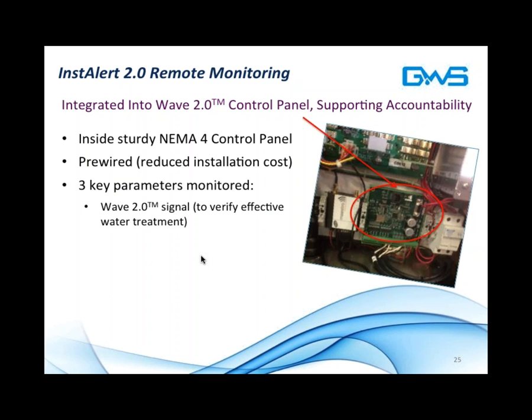The first is that the Wave is doing its job, which is to say that effective water treatment is taking place, another way of ensuring that scale is under control, corrosion is in check, and biological growth is effectively being treated. The second parameter is conductivity of the recirculating condenser water. This allows us to infer if there is a system hiccup. So, for example, if a blowdown valve sticks open, that means water is going to drain from the tower, and new makeup water will come in to meet the level meter. When that happens, conductivity will drop below our set point, and we will know that there is a leak in the system, a valve stuck open, or perhaps there's been heavy rains. The same is true if the valve sticks closed. Conductivity will spike, and to avoid scaling the tower, we will know that very, very quickly.